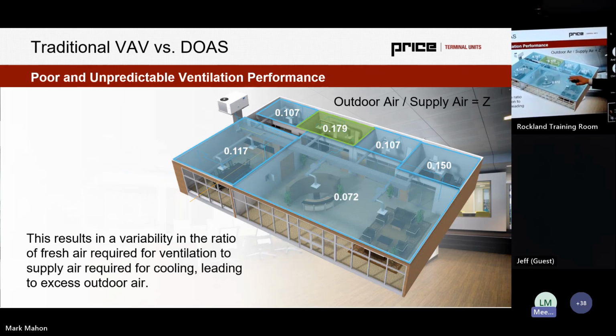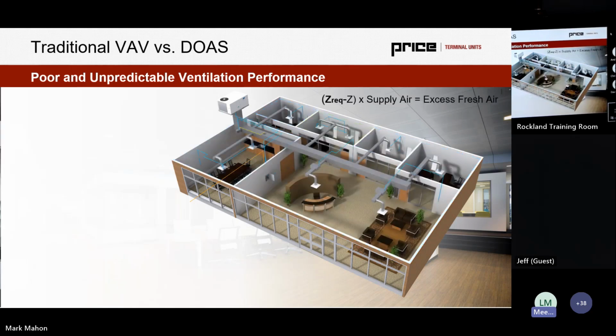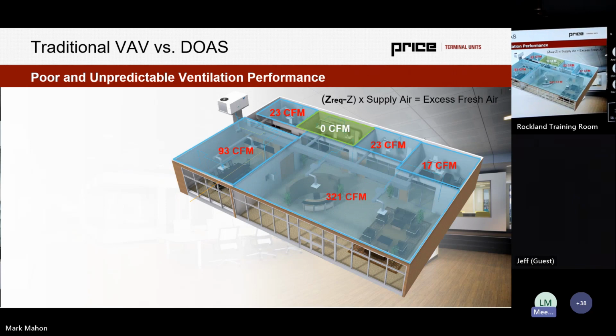So in this case, the highest ratio of ventilation air to supply air is going to set that ratio for the air handler and for every other zone served by that air handler. Often firms might just have, for different applications, certain rules of thumb for percentage of ventilation air to supply air. However, if we were going to calculate it out zone by zone, this would be the type of approach you'd be taking to figure out how much ventilation we actually need to total supply on design day. And with that required ratio, we then can also look at the required ratio versus the ratio we need. And through that, we'd be able to calculate excess fresh air. So this is under the assumption that we're actually matching that required maximum ratio.